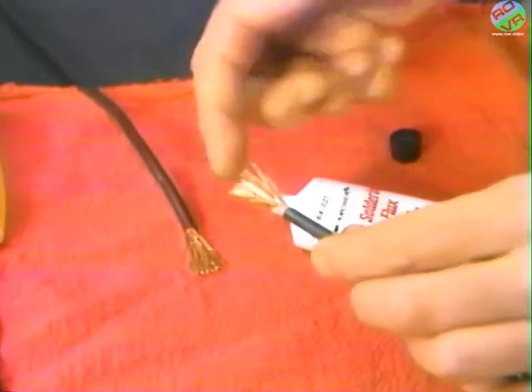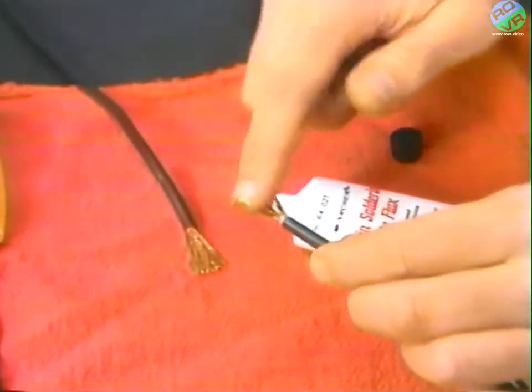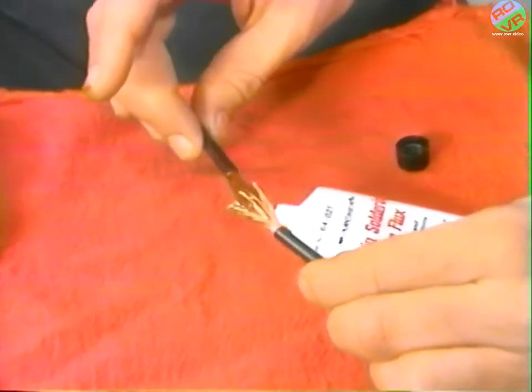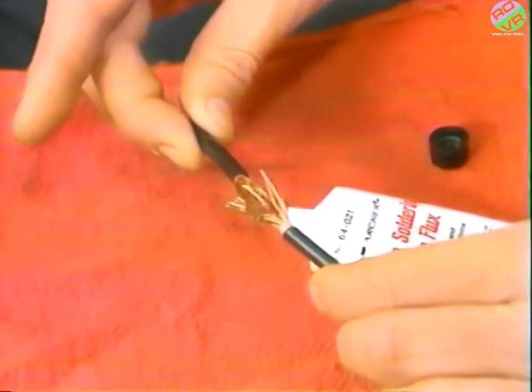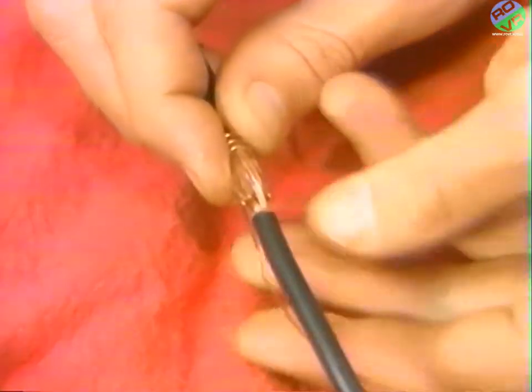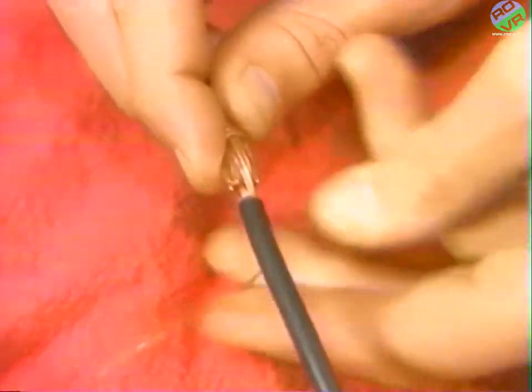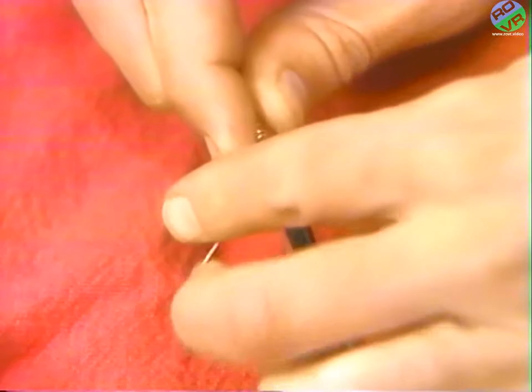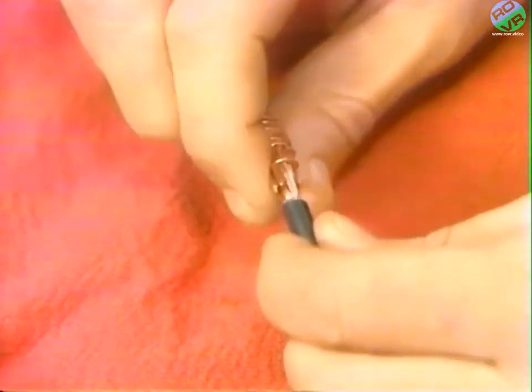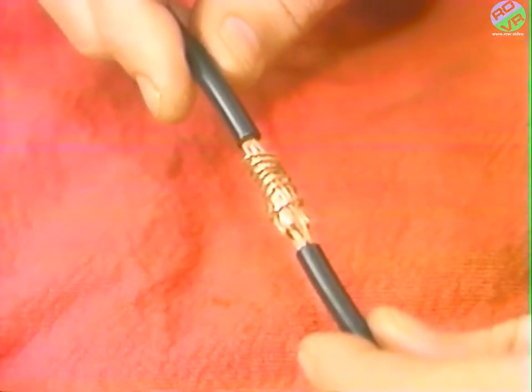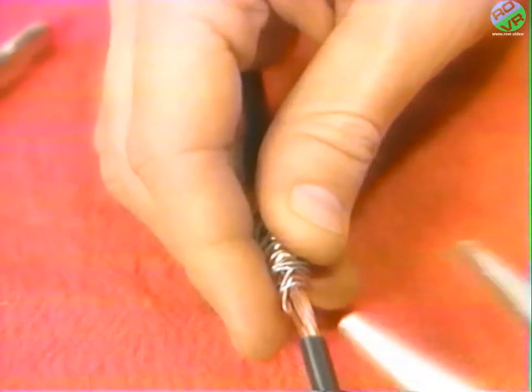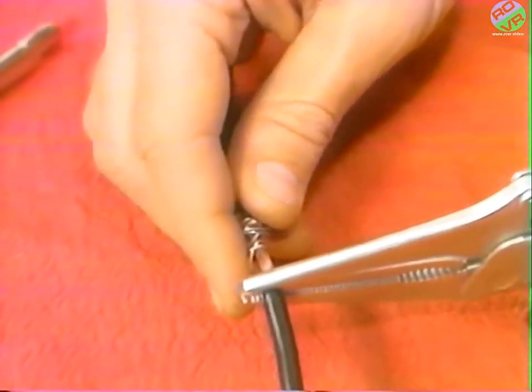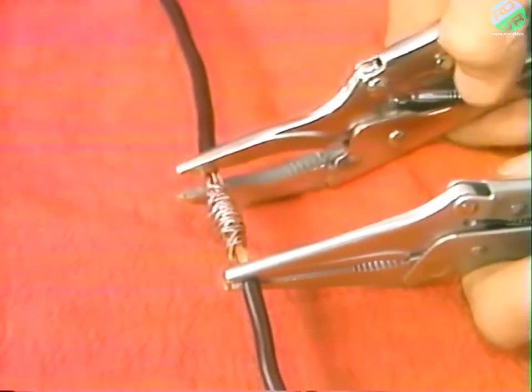Apply rosin flux to the strands of each wire and interweave the strands of the 2 wires. Also, wrap a single piece of wire strand tightly around the joint to hold the 6-gauge wire strands together. This wire strand can be obtained from the 6-gauge wire that you're replacing. Wrap solder around the joint and place vice grips on both sides of the joint to act as heat sinks.